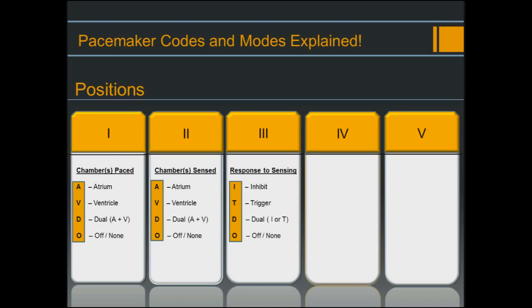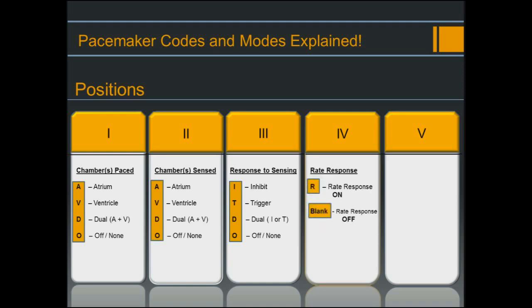The options for position three are: I for inhibit, meaning the pacemaker will pace in the given chamber unless it senses intrinsic activity, in which case it will inhibit or withhold pacing; T for trigger, meaning the pacemaker is capable of triggering an AV delay; D for dual, meaning inhibit and trigger; and O for off. You should never actually see a device with T programmed in the third position — pacemakers should only have D, I, or O. We really only talk about T to understand the concept of triggering an AV delay.